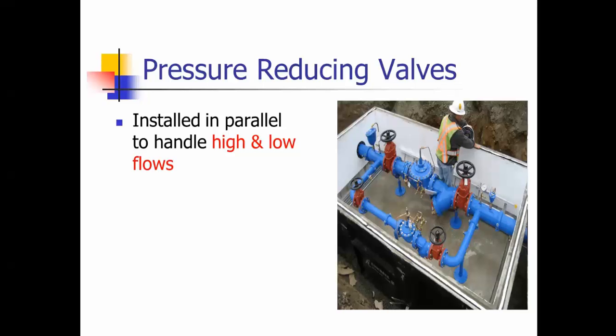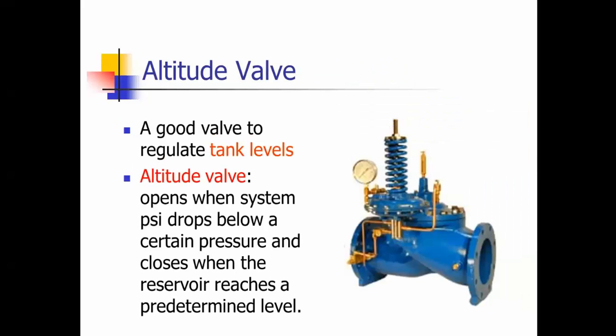Pressure reducing valves, they are used in parallel to handle high and low flows. You can see there's a larger regulator, and then there's a bypass to the left of the larger regulator, and so they're used for high and low flows. An altitude valve is a good valve to regulate tank levels. They're set to open when a tank gets down to a certain level, and then when it gets full, it shuts off. So anyway, those levels are set.